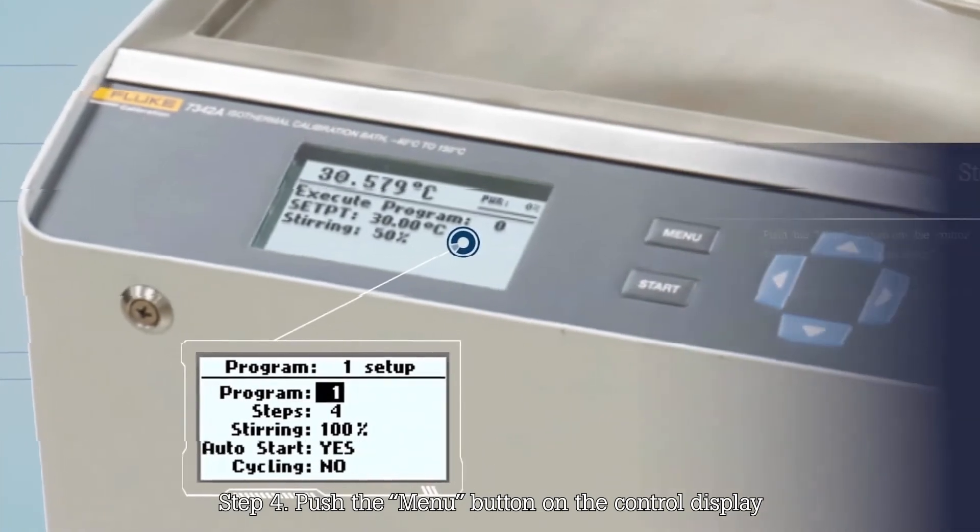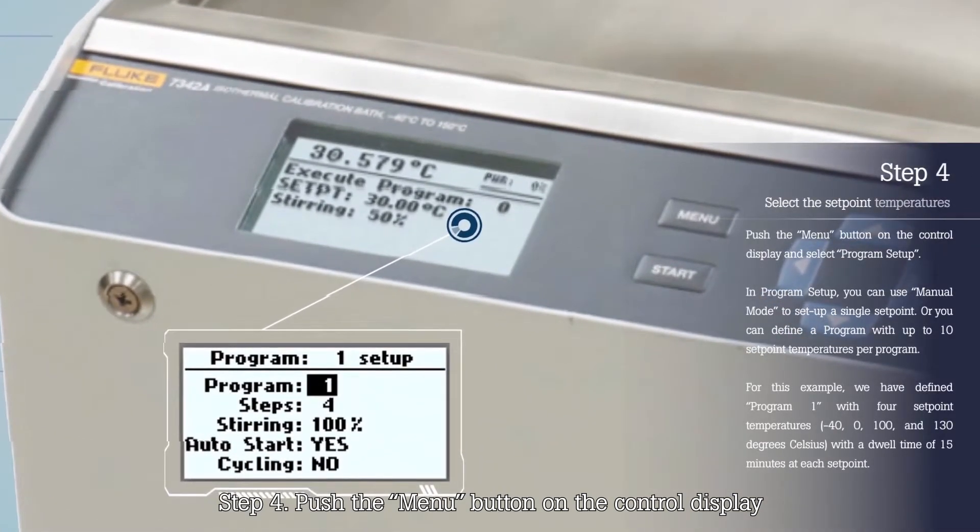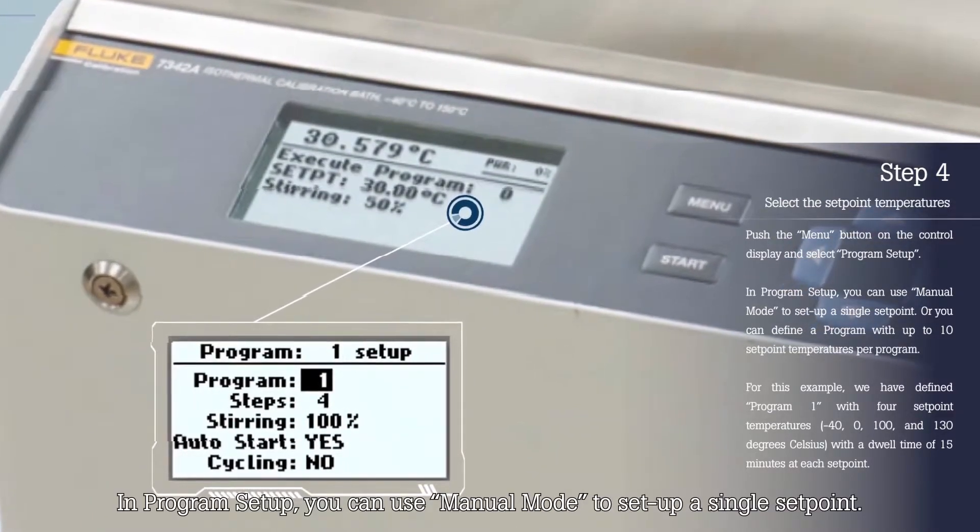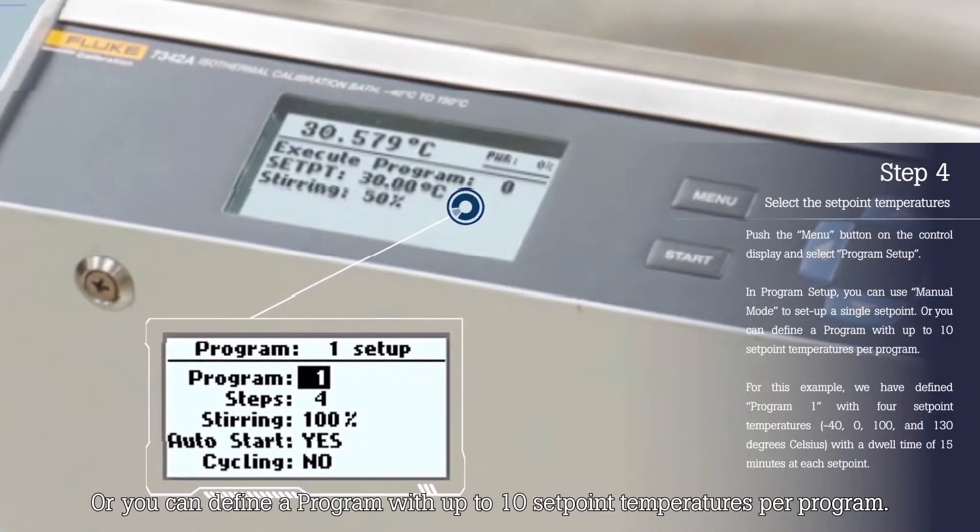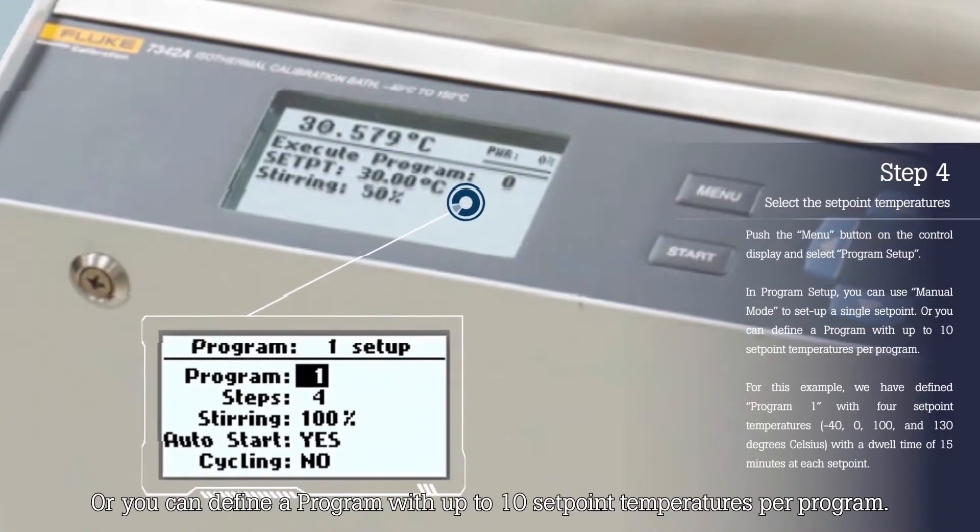Step 4. Push the menu button on the control display and select Program Setup. In Program Setup, you can use manual mode to set up a single set point, or you can define a program with up to 10 set point temperatures per program.